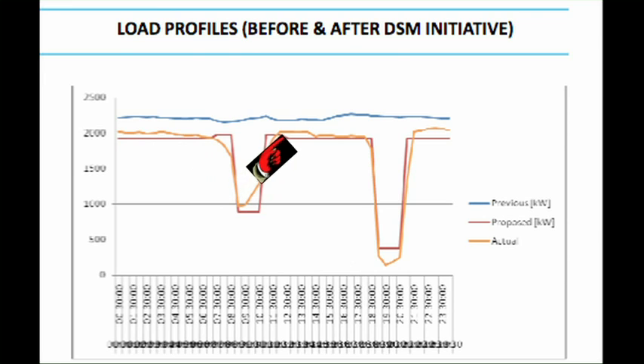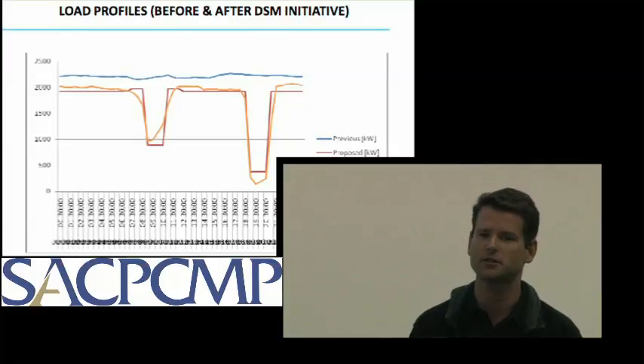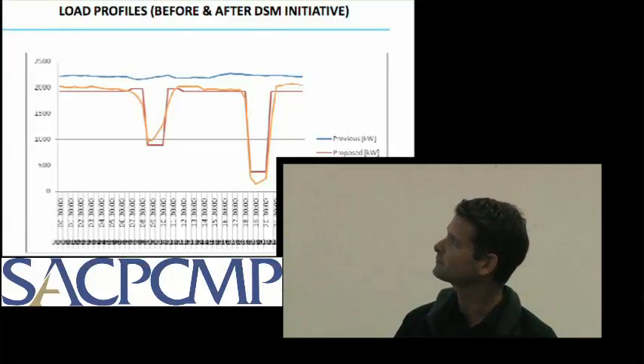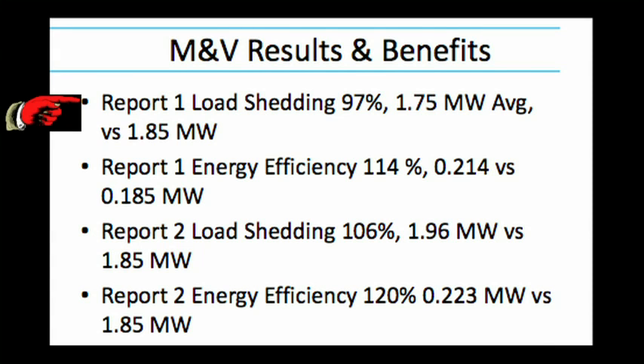From the M&V results, so now when you're doing a proper DSM project, you get the university team to come and verify it. Gershwin actually was initially arguing with me about what's load shifting and energy efficiency at the beginning of the project, and then he handed it over to someone else. So these are the M&V results. We guaranteed 1.85 megawatts, and you're allowed to be within 10% of that. So the first set of results we got 97%, and energy efficiency we overachieved. And the second results we did better, and better for the third results, and they've been running, and recently did another set of M&V results, and they were still fine.